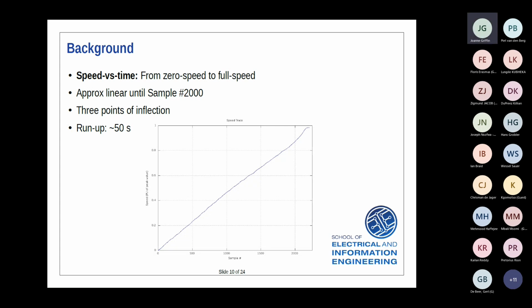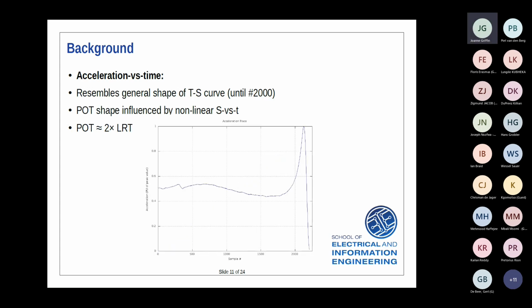Anyway, if we take that and we differentiate it, so we're looking at the gradients now. How does the gradient change? You can see it's relatively constant up into about the sample point 2000, and then it climbs very high towards the pull-out torque. So there's huge acceleration towards the end. And you can see there's more or less 5 regions. So there's a negative over here, positive, negative, positive, etc. So there's 5 clear regions.